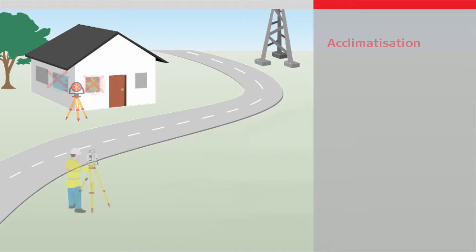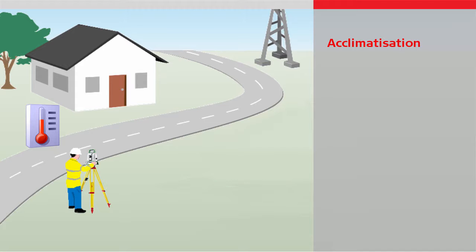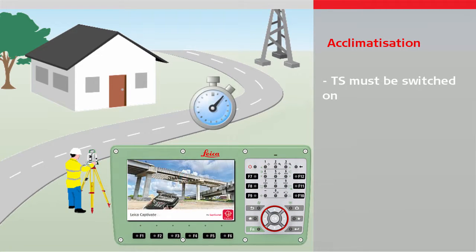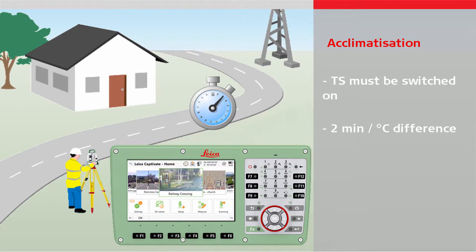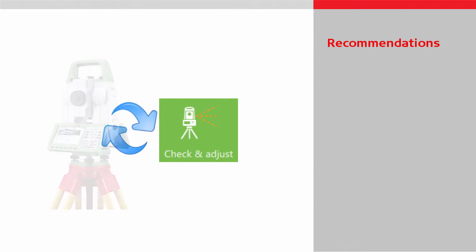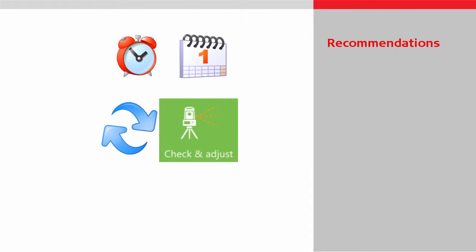Before starting one of the calibration routines, the instrument must be acclimatised to the ambient temperature. The instrument must be switched on and needs approximately two minutes per degree Celsius difference to acclimatise, with at least 15 minutes to minimise a heating-up drift. To guarantee the highest precision during daily work, we recommend calibrating the instrument on a regular basis, every three to six months.